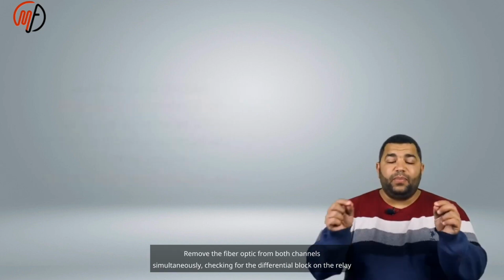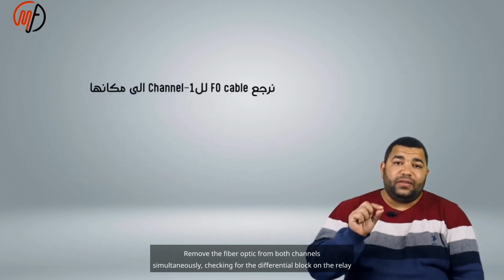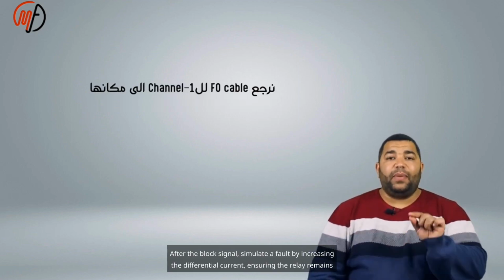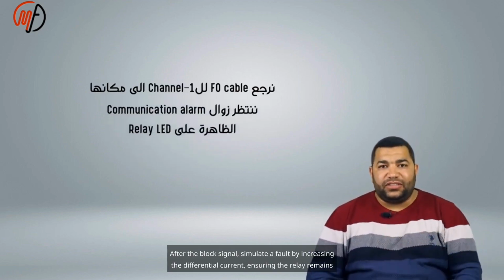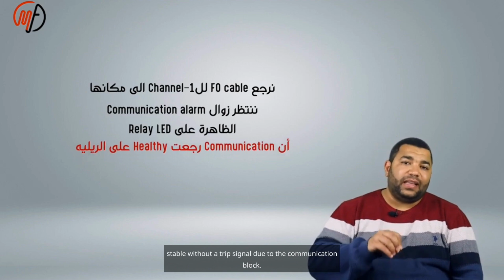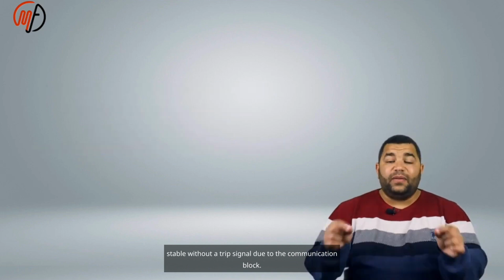Remove the fiber optic from both channels simultaneously, checking for the differential block on the relay LED. After the block signal, simulate a fault by increasing the differential current, ensuring the relay remains stable without a trip signal due to the communication block.